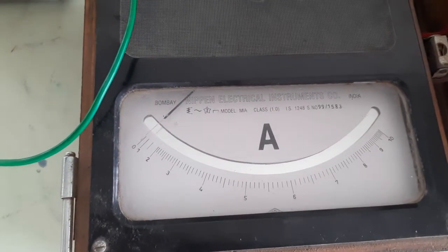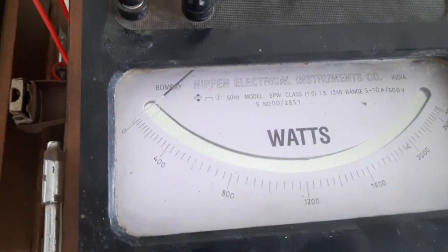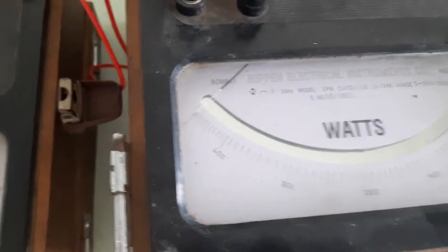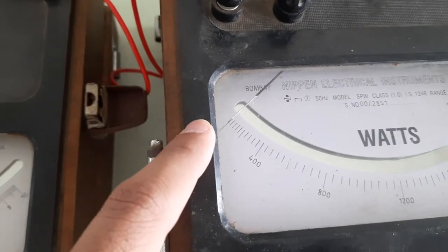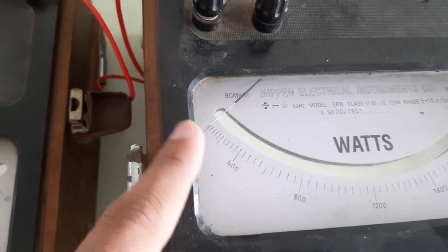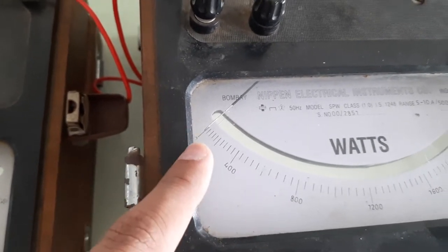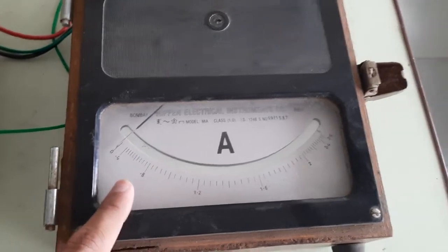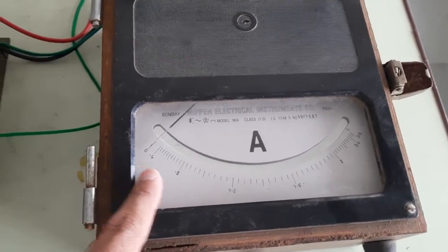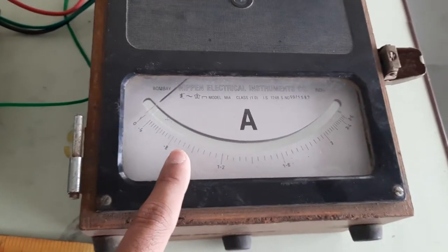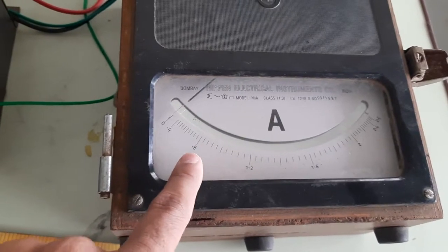Initially no load is connected, so this will be the first reading, for no load. Then gradually we will switch on the load. At no load it will show a minor current on the primary side and a minor wattage. For this wattmeter, one reading will be 40 watt, because between 0 and 400 there are 10 lines, so one line is 40 watt. Then on the secondary side, this is the ammeter. It shows readings from 0 to 5, but the scale is given for 0 to 2.5, so there is a multiplying factor of 2. Whatever reading comes, multiply by 2.